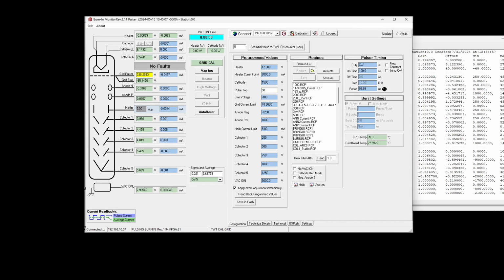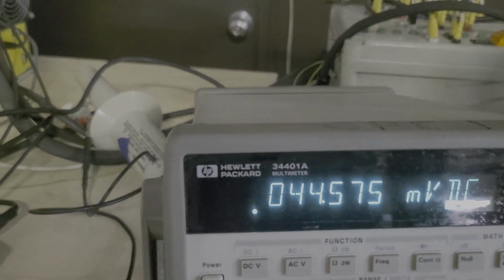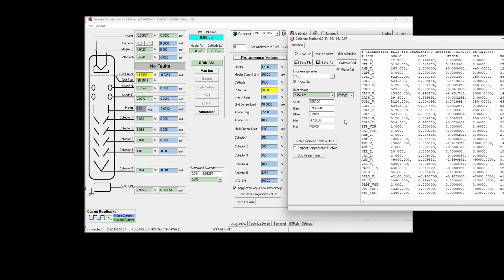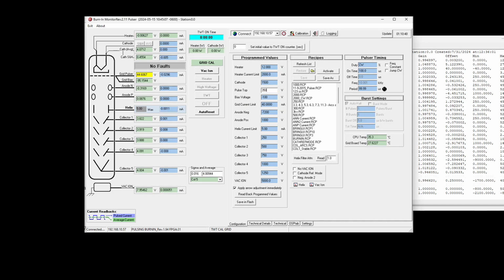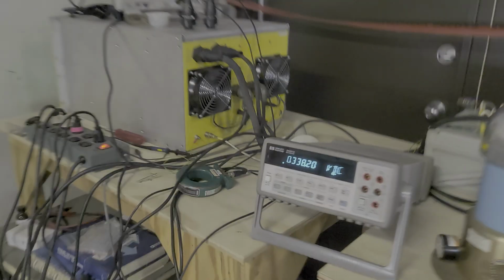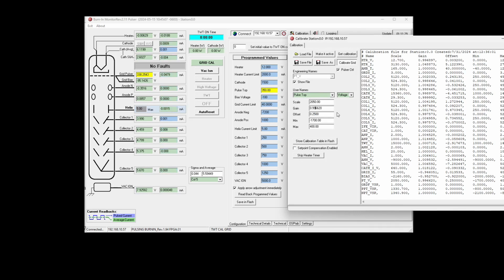Now, let's drop it back to 50 and check that number again. 44.79 was our previous. Let's see how much it's drifted. And we have 44.6. Let's adjust offset. It's actually really close already. We're going to leave it there, and then bump this to 350 again. Check the drift on the meter. 338.2. At the high end, we adjust gain to make 338.2.0, like so.